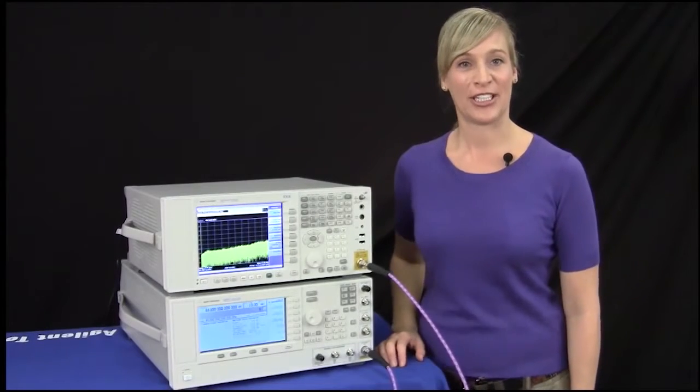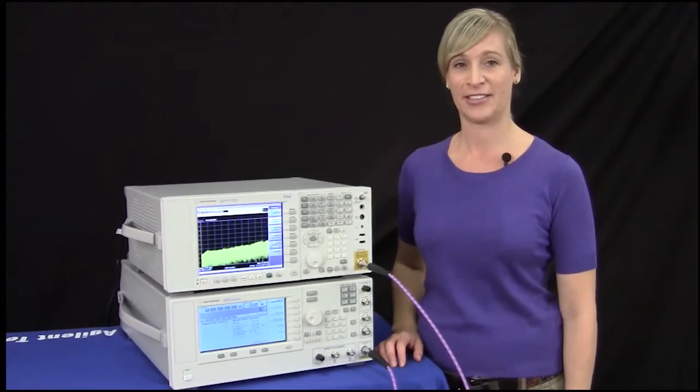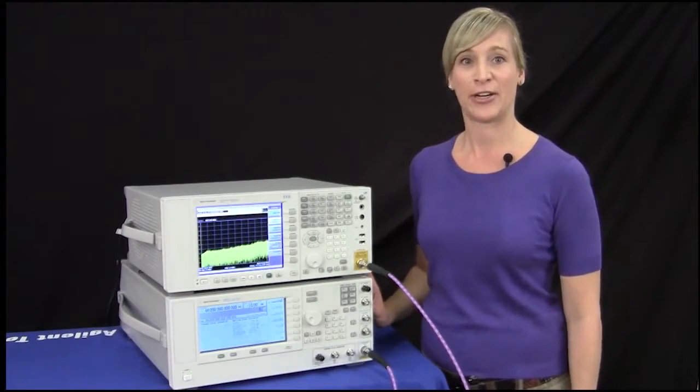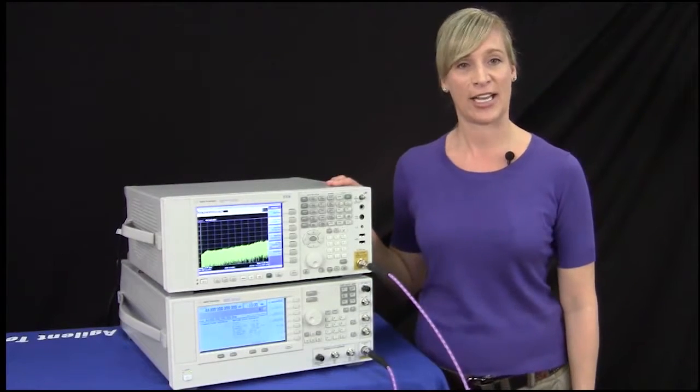For my first demonstration I'll show you the EXA's performance at 44 gigahertz. For the setup we have the PSG signal generator outputting a 44 gigahertz signal to our EXA signal analyzer.